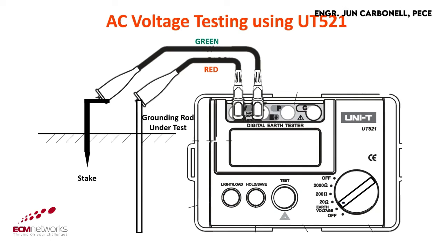Before doing the earth resistance testing, measure first the voltage on the ground rod to be tested with respect to ground. Insert the simple test leads, red and green, to the voltage port and the ground port of the UT521. Clip ends of the probes to the ground rod and the auxiliary earth stake inserted to the soil.